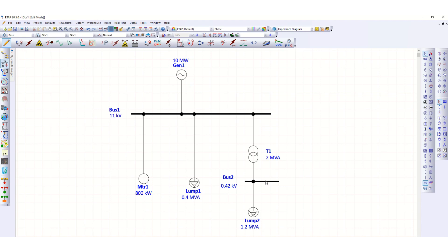Another way, which is the main topic today, is by changing the tap of the step down transformer. So here I have connected this 2 MVA transformer, 11 kV by 420 volt.